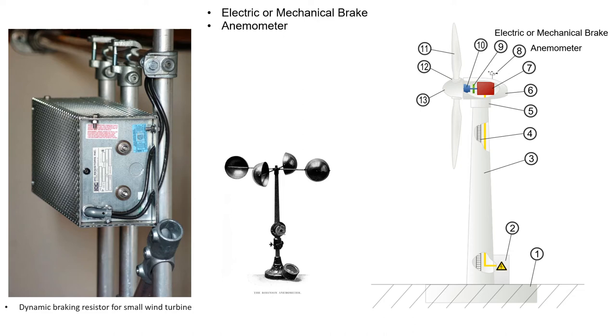The electrical braking system of a small wind turbine can be done by dumping energy from the generator into a resistor bank, converting the kinetic energy of the turbine rotation into heat. This method is useful if the electrical load on the generator is suddenly reduced or is too small to keep the turbine speed within the allowed limit. Cyclically braking causes the blades to slow down, which increases the stalling effect, reducing the efficiency of the blades. This way, the turbine's rotation can be kept at a safe speed in faster wind conditions while maintaining nominal power output. This method is usually not applied on large grid-connected wind turbines.